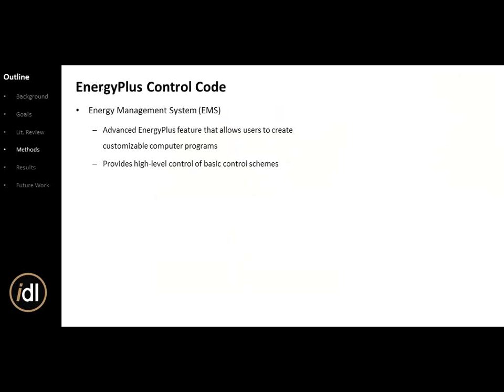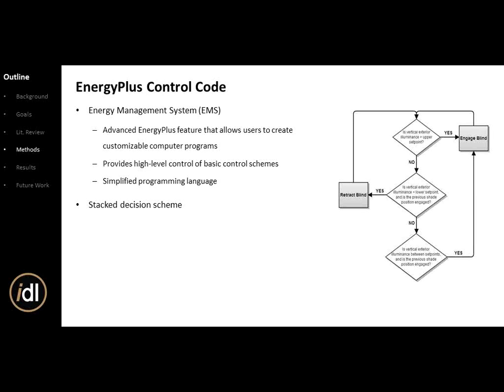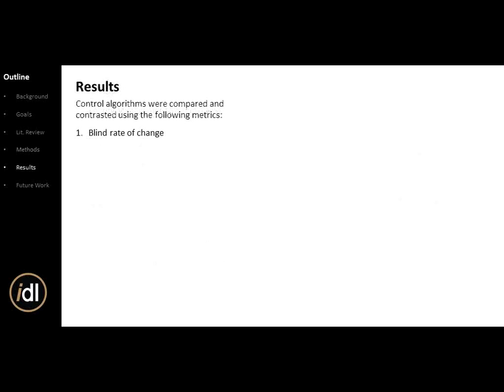The EMS system is a customizable computer program for high-level control. It takes a lot of time and effort because you essentially have to become a computer programmer. It uses a simplified language, a stacked decision scheme, conditional programming, and importantly, trend variables — you can collect data over time, such as window position over the last three hours, which is a huge part of my programming.